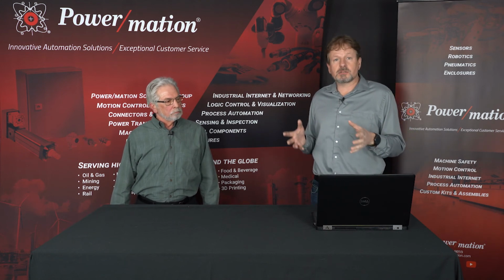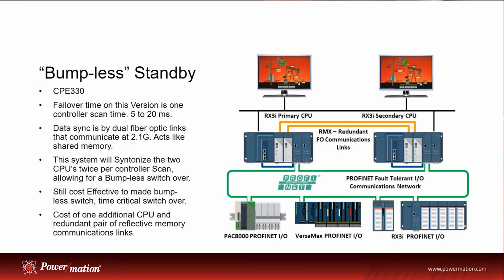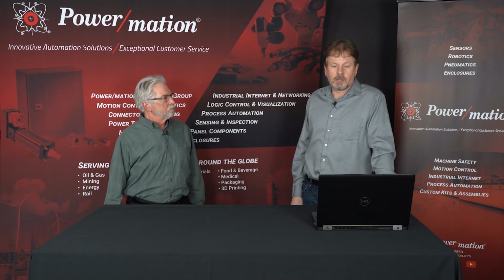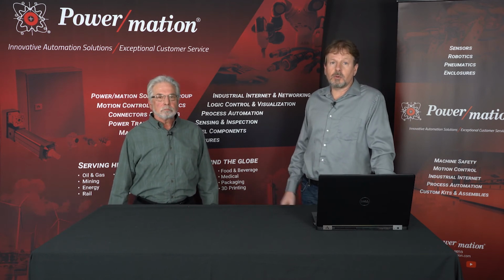And that's why we have a system that's called bumpless. And bumpless standby is where both processors are running the exact same program at the exact same time, synchronizing the data like Rocco said, so that if one fails, the other one instantly takes over, and now you're controlling your I/O. So basically, if one CPU goes dead, we take over the same scan. Correct, exactly.